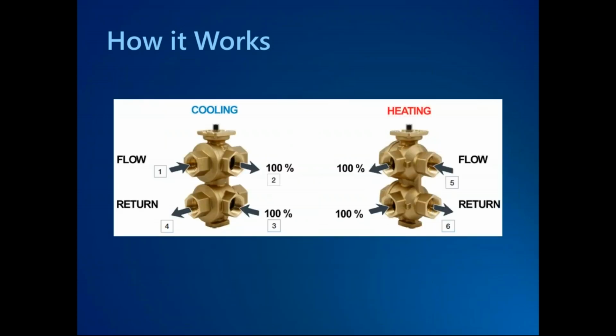Another way to look at this is just cold water flows in through port 1, out through port 2 to your zone, back through port 3, and then back to your mains on port 4. And then when you rotate that stem 90 degrees, you now have ports 5 and 6 interacting with ports 2 and 3. So again, we aren't reinventing the wheel here. There's not a whole lot of new technology. It's just a better mousetrap when it comes to providing a compact solution for a problem that has come to light recently in the market with this use of chilled beams.